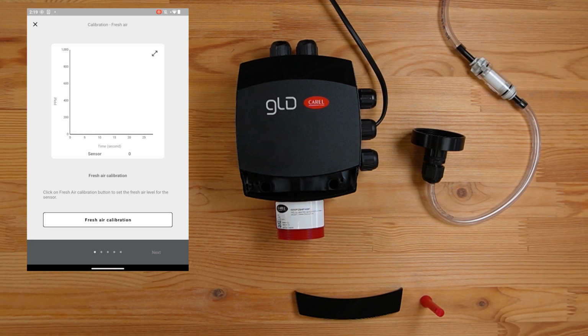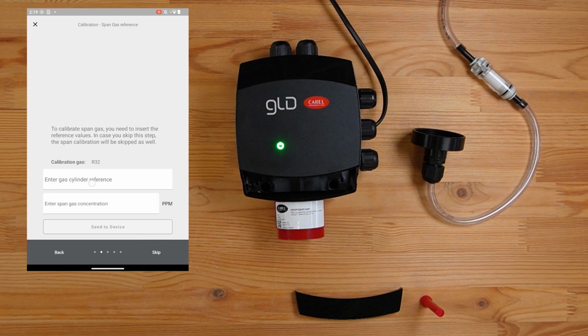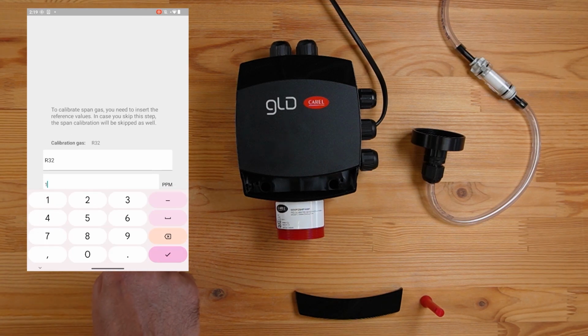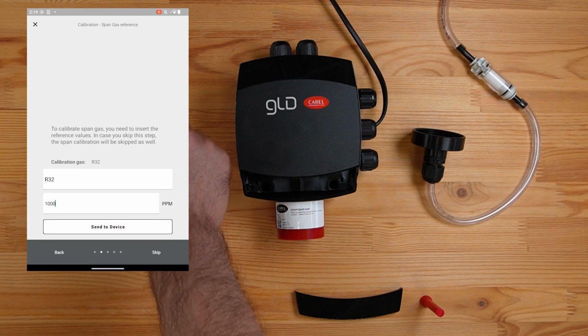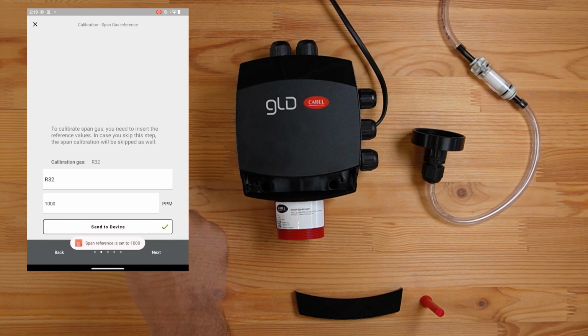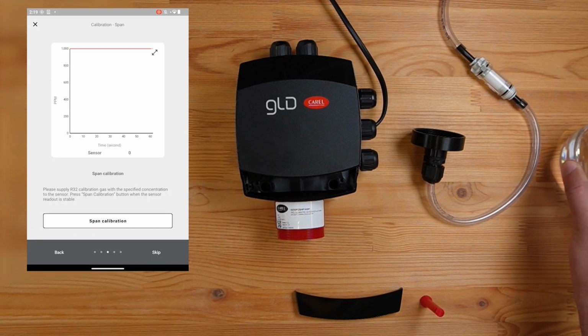Click Fresh Air Calibration at the bottom, then select Next. To perform the calibration, the specific gas indicated as the calibration gas needs to be used. Enter the gas cylinder reference, serial number of the reference gas, or other information to be shown on the certificate. Enter the concentration of the gas used for calibration. Click Send to Device to set the gas concentration used for calibration.